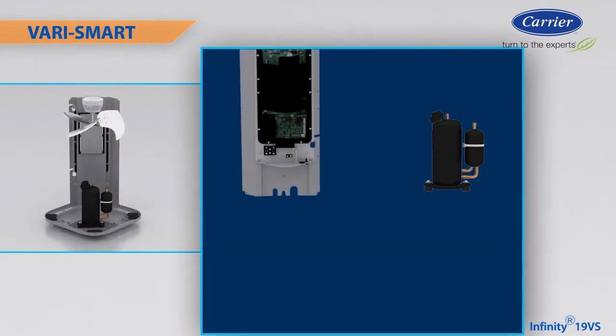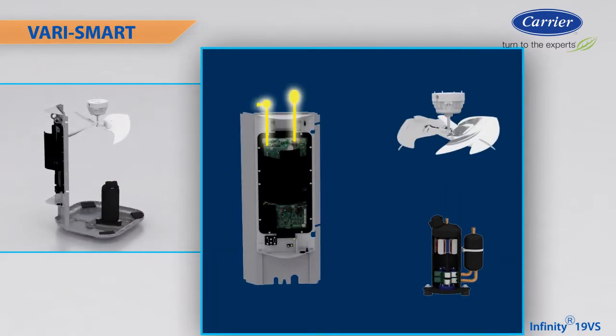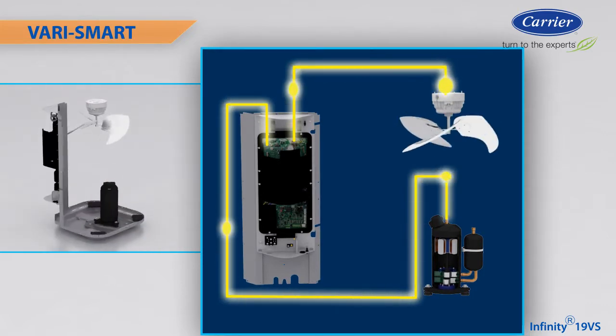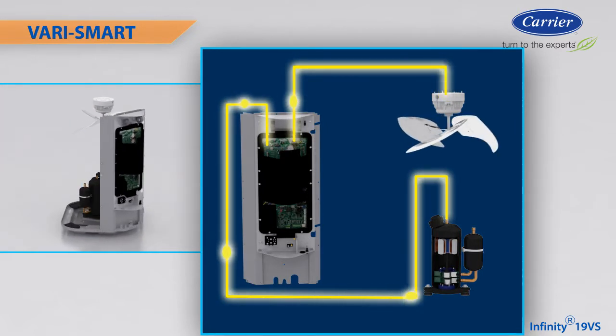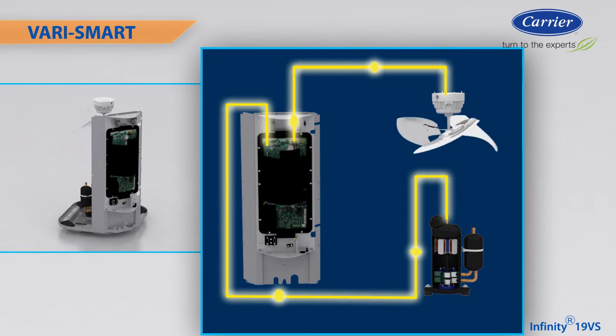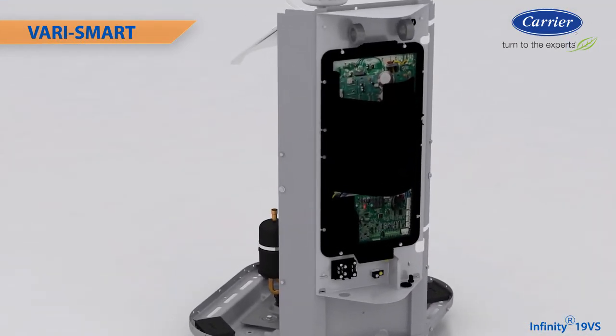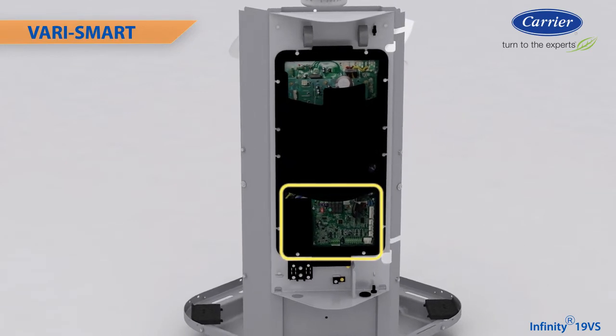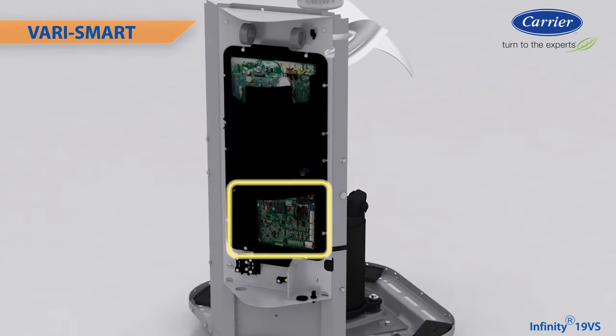The new integrated inverter in the Infinity 19VS drives both the compressor and fan motor. It monitors temperatures and electrical characteristics and ensures the system operates within reliable limits. If it senses the approach of an undesirable operating condition, it will take action to avoid the situation. The inverter also features a replaceable air conditioner control board section to allow for future repair without changing the entire inverter assembly.